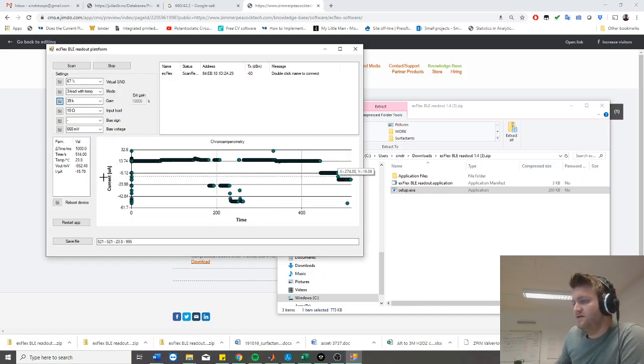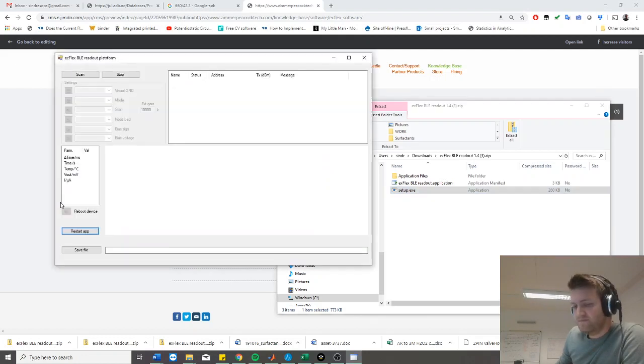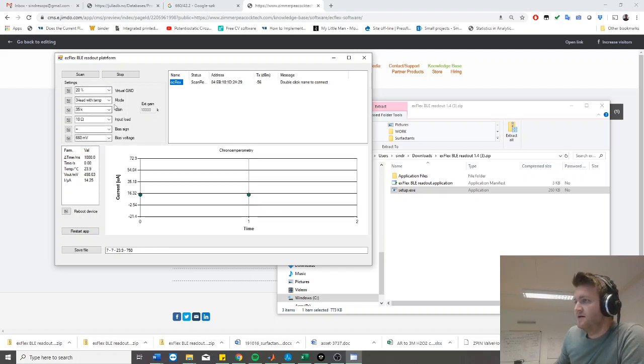And finally, there's one more setting that you now can do, and that is a complete software reset of the circuit. So if you hit this button, it will reboot your device without you having to power cycle it. And let's scan and see if we can find it. There it is. And now it should restart at a time close to zero. So it's restarted the timer, it's restarted the settings. The settings that we put there before have been reset to the default settings.